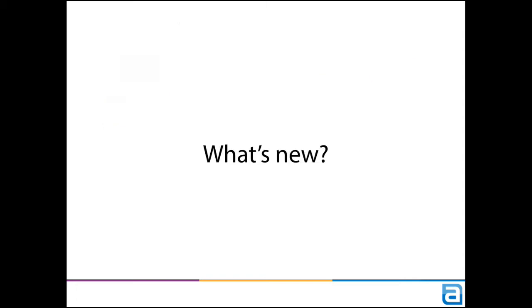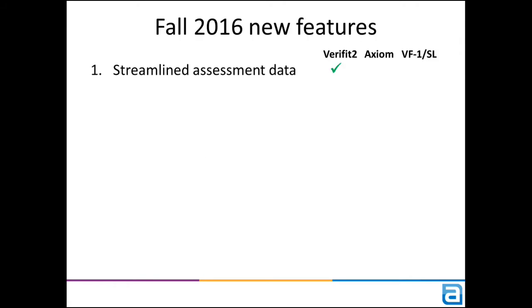So, what's new? Streamlined assessment data entry for Verifit 2. Monitor headphone level boosts, also for Verifit 2. The range of the binaural monitor headset has been increased to allow for easier listening to hearing instruments programmed for mild to moderate losses.